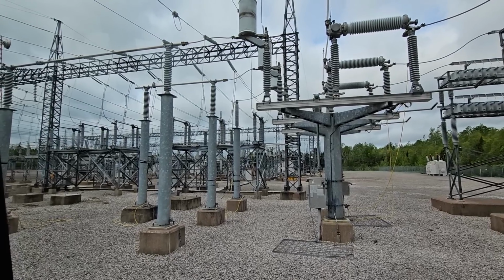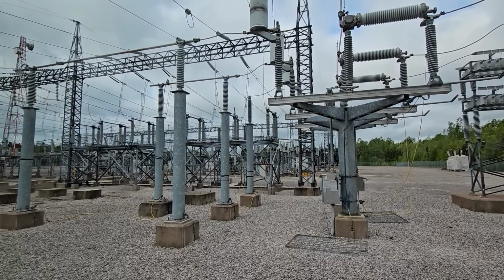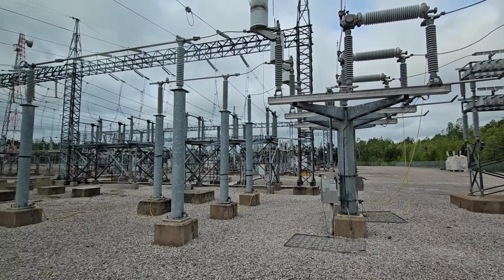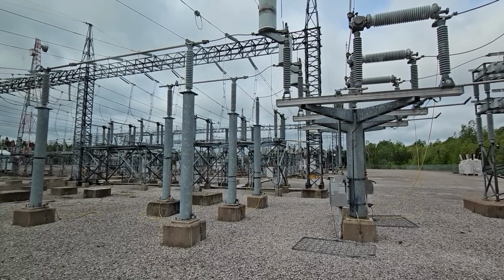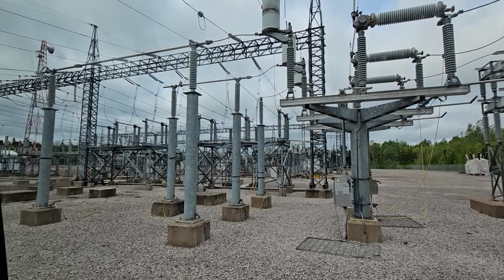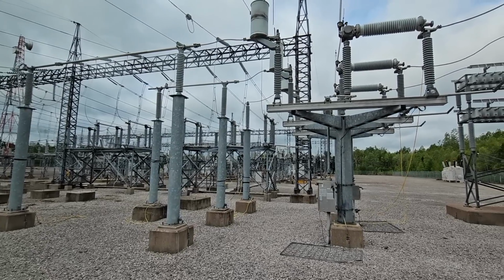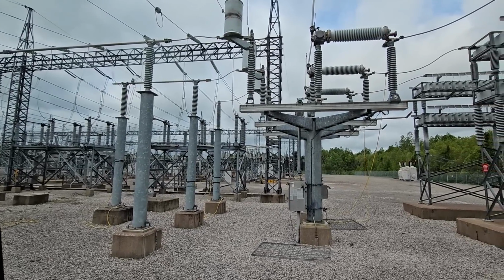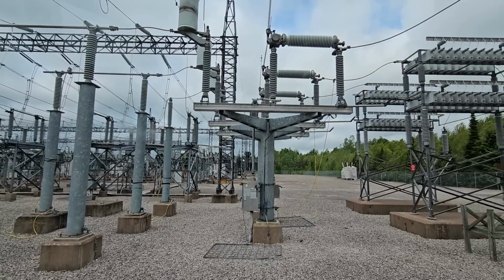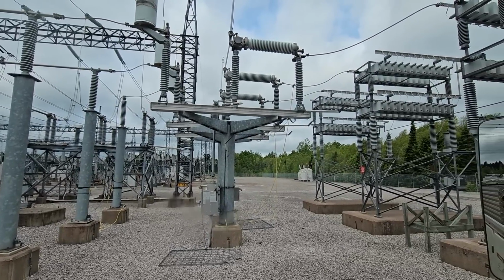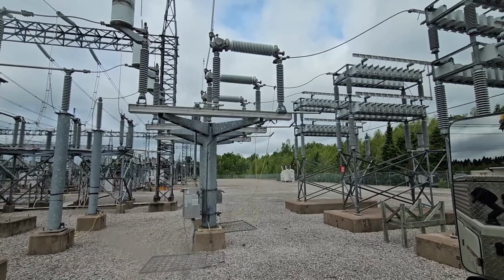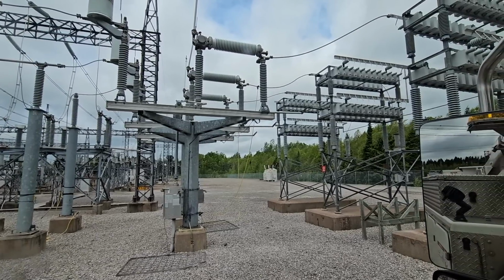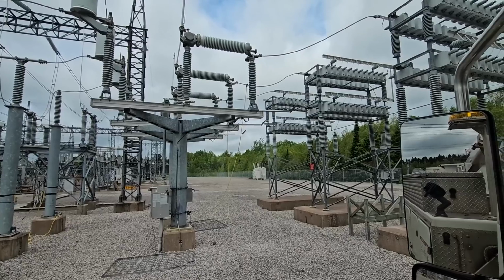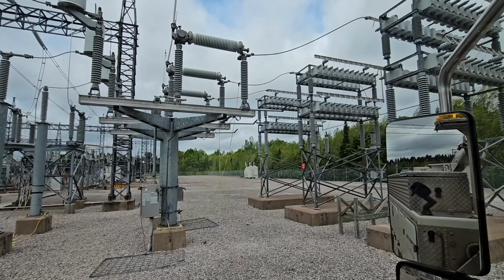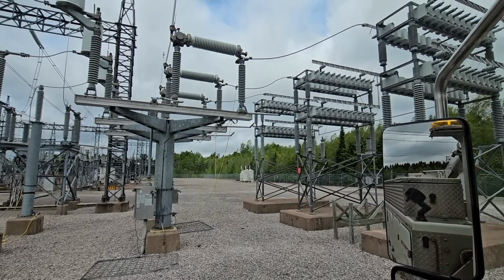So all these myths online about being billed for those losses, that's not true. The smart meters can read the power factor. They have the capabilities of billing for kVA, but that's not something we do for residential customers. When there's a bad power factor on the line, we as a company, even if only 90% of that power is being used because of a lagging power factor, we have to generate that larger number, that 100%.